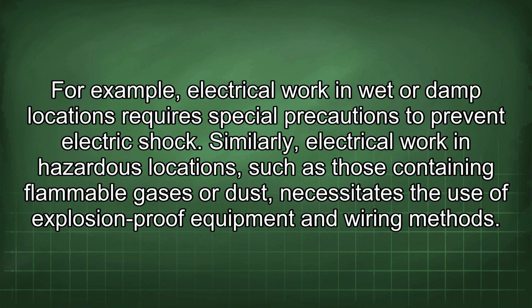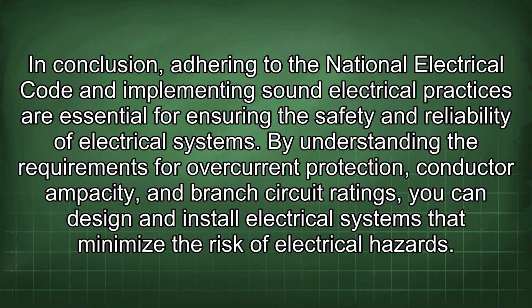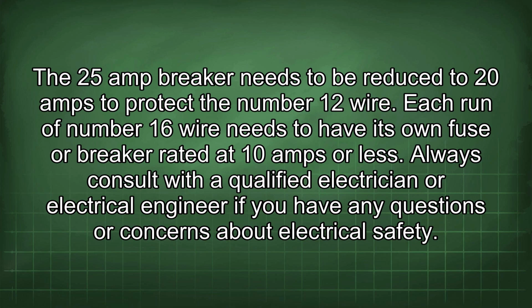In conclusion, adhering to the National Electrical Code and implementing sound electrical practices are essential for ensuring the safety and reliability of electrical systems. By understanding the requirements for overcurrent protection, conductor ampacity, and branch circuit ratings, you can design and install electrical systems that minimize the risk of electrical hazards. The 25 amp breaker needs to be reduced to 20 amps to protect the number 12 wire. Each run of number 16 wire needs to have its own fuse or breaker rated at 10 amps or less. Always consult with a qualified electrician or electrical engineer if you have any questions or concerns about electrical safety.